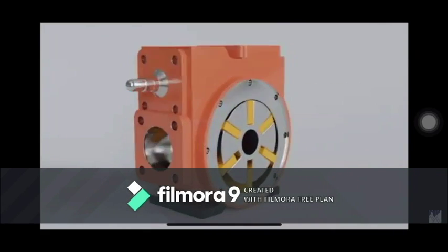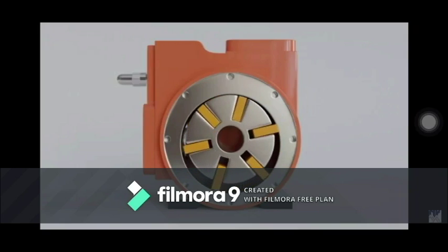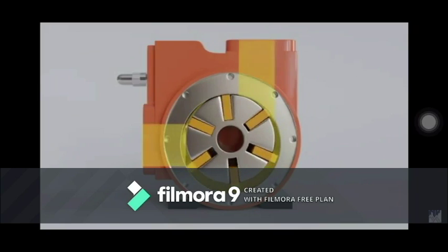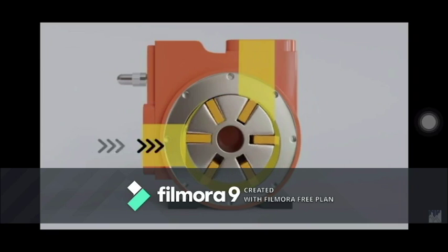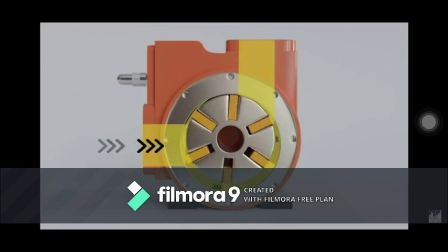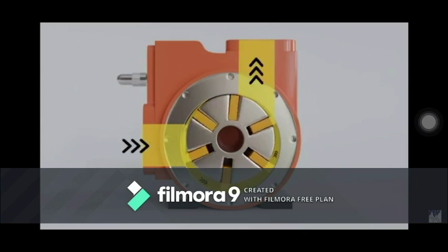The rotor is sealed in the cam by two side plates. Vanes or blades fit within the slots of the impeller as the rotor rotates and fluids enter the pump. Centrifugal force, hydraulic pressure, or push rods push the vanes to the walls of the housing. The tight seal among the vanes, rotor, cam and side plates is the key to good suction. The housing and cam force fluid into the pumping chamber through holes in the cam. Fluids enter the pockets created by the vanes, rotor, cam and side plates.